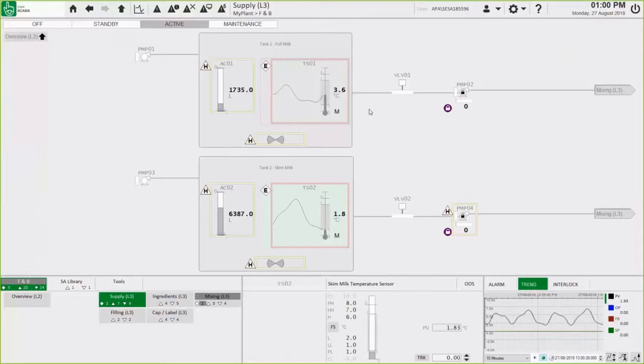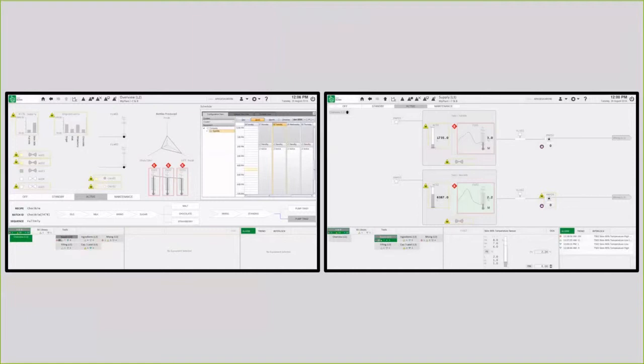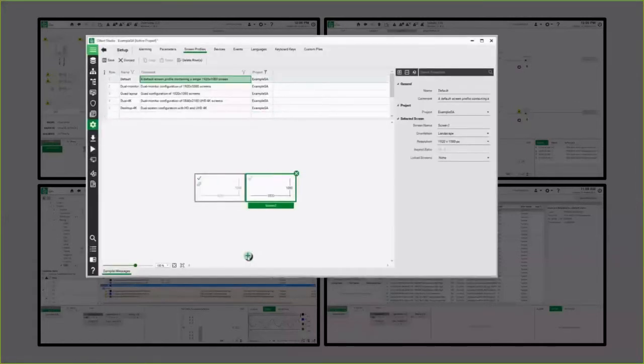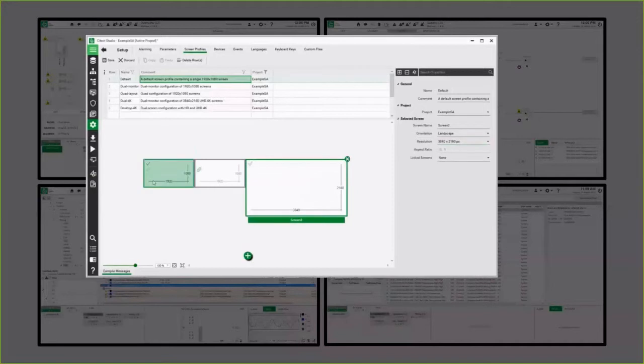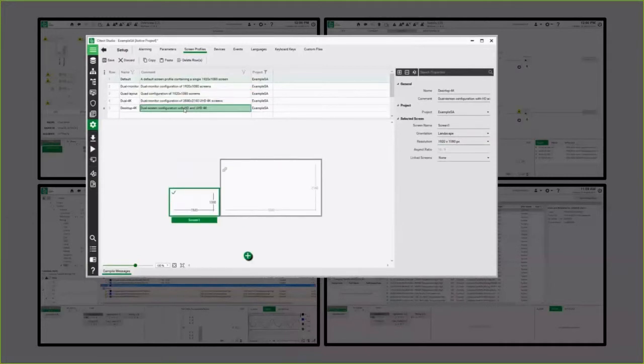Let's now have a look at what situational awareness looks like in a multi-monitor environment. Here I have CITECT 2018 spread across two monitors — I could also have four monitors. What is new is the ability to change your monitors and save that as a screen profile for later use. I can add multiple monitors, change the resolution, arrange my monitors as they actually are in the control room, save these as various profiles, and allocate them to a specific machine whether it be an engineering machine or a control room PC.